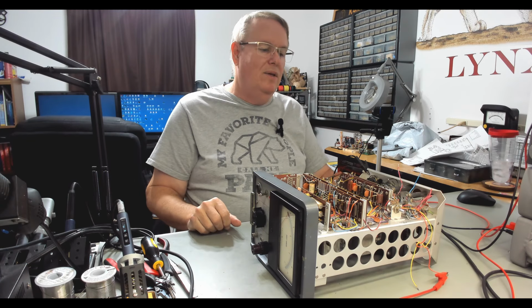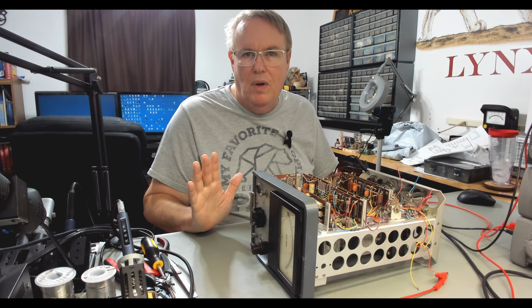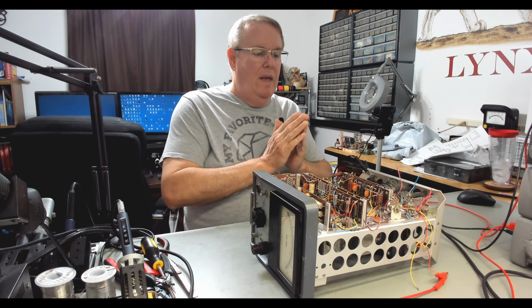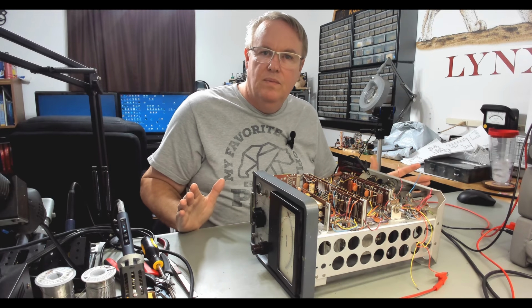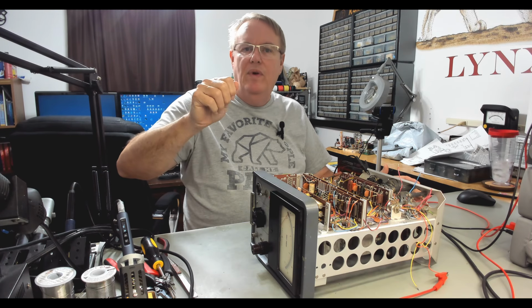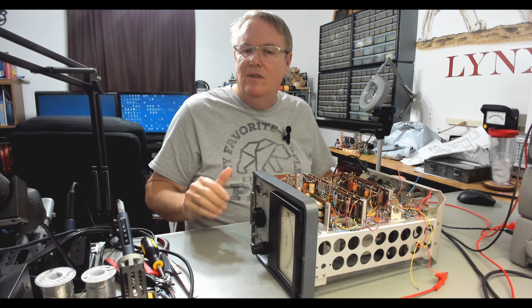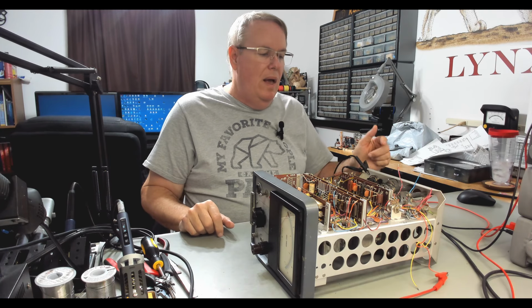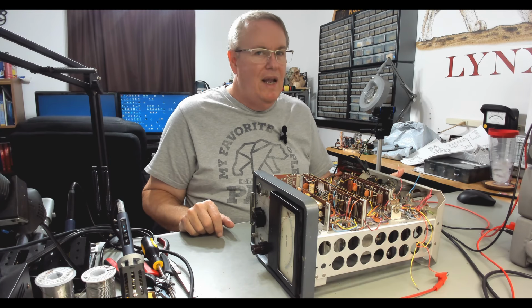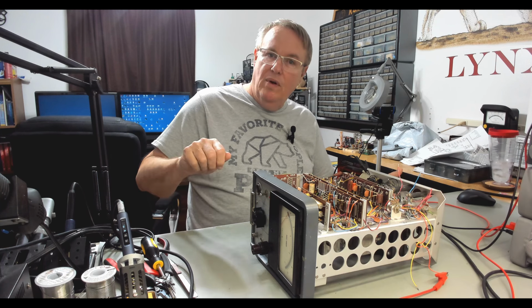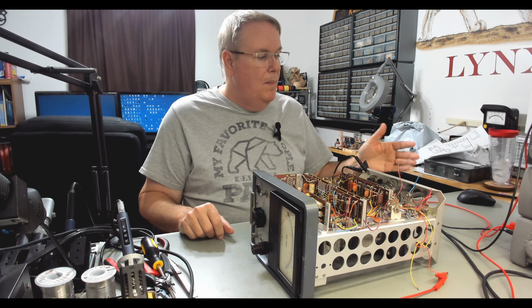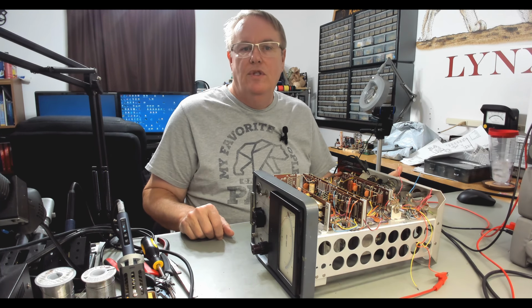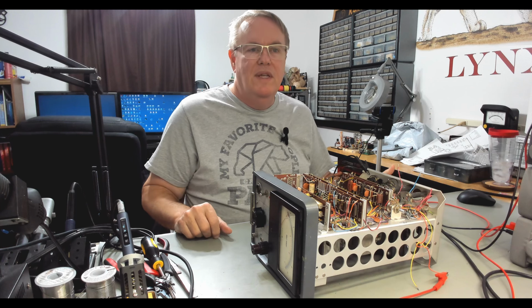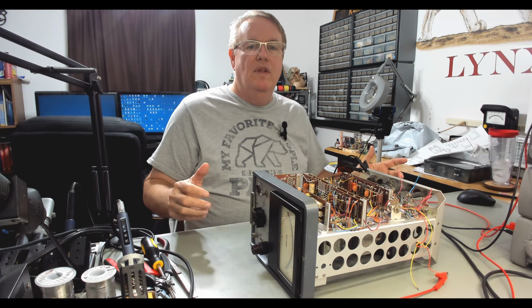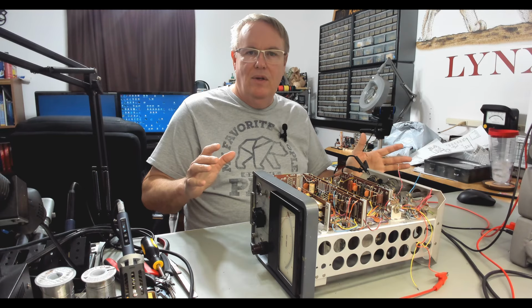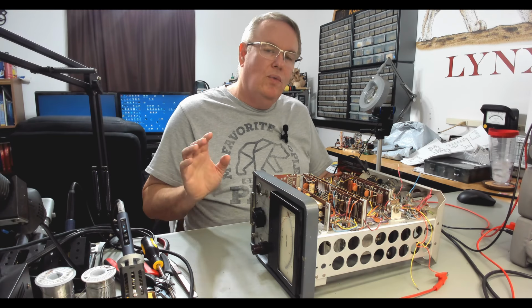So then I had the idea that maybe my mods caused the problem, right? So I went back and undid all the mods, got it back to where it had the same 20 volt variation and the same voltage range, acting just like it did before I touched it. I did this test and it acted exactly the same. I could only vary the voltage a small amount, but it acted the exact same way. The voltage dropped, basically 10 volts, with any load. Removing the load, it did not appear to be trying to hold the voltage.